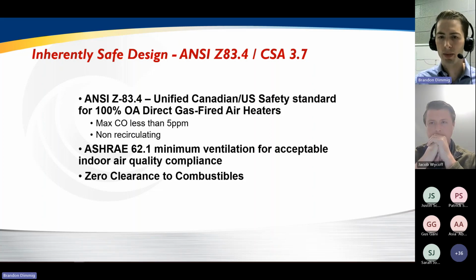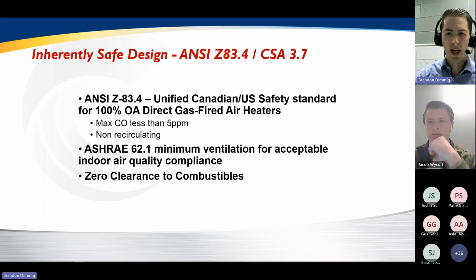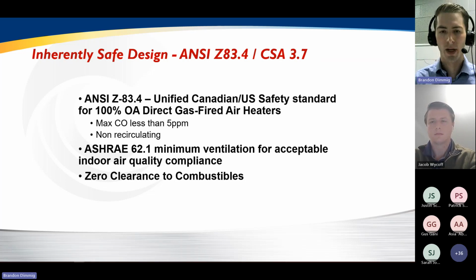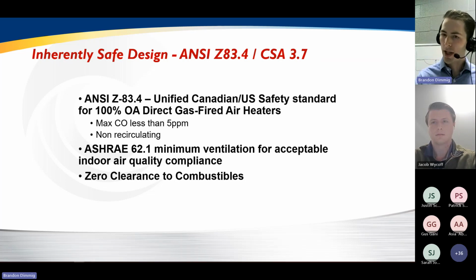important one. The second one is the non-recirculating nature of these units. Being that we're not recirculating indoor air, you cannot build up carbon monoxide in the space. You always must be bringing in outside air. Actually, the outside air is what allows this unit to bring in air and support an ASHRAE 62.1 minimum ventilation. And so we know intrinsically that the outside air is helpful, but it's particularly important in the context of a direct-fired unit that the outside air is always coming in when there's combustion, because we don't want to build up any harmful combustion byproducts.